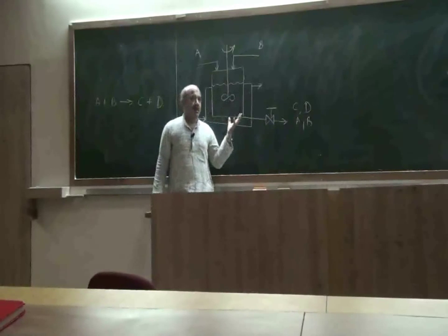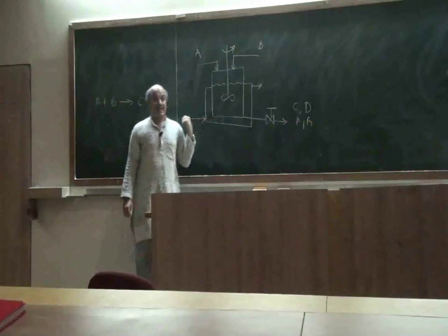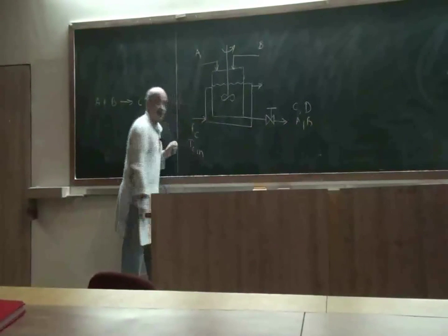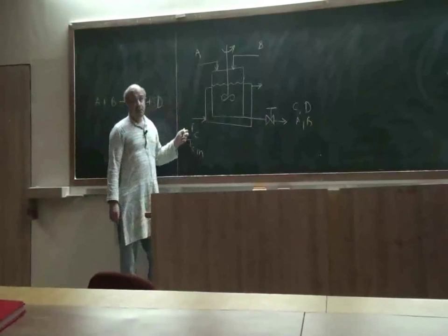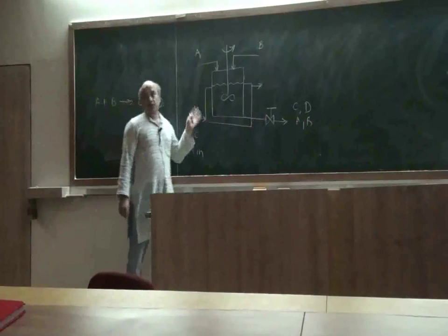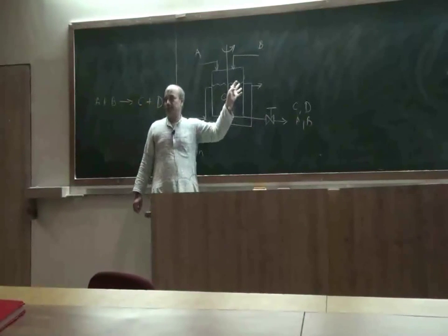You're pumping at the same design flow rate, but the coolant inlet temperature is changing, so this T_c,in is changing. If you keep pumping the fluid at the same design flow rate, you are making a mistake, because it's not going to remove the heat the way you want it.